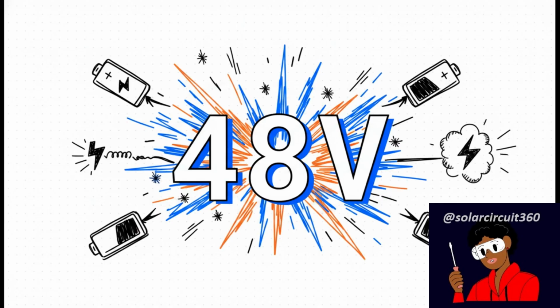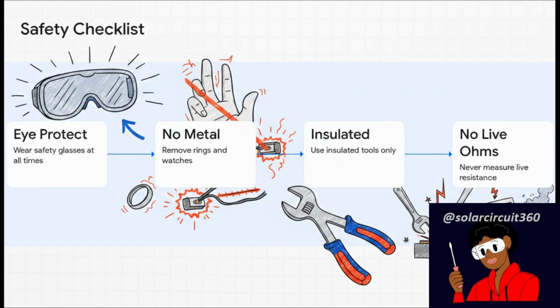Plus, if shorted out, these systems can dump hundreds or even thousands of amps in a fraction of a second. It is absolutely no joke. So you absolutely have to stick to this safety checklist. Number 1, wear eye protection, always. Number 2, take off your rings, watches, and any metal jewelry. A metal ring shorting across battery terminals turns into a glowing hot heating element instantly.